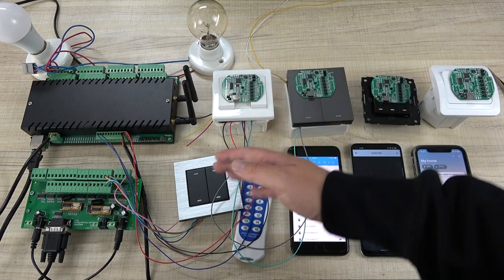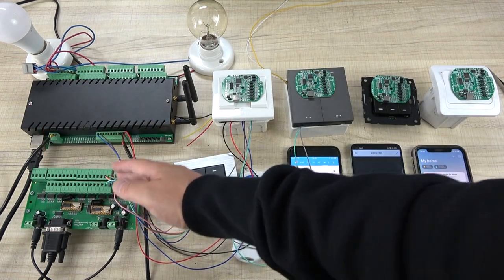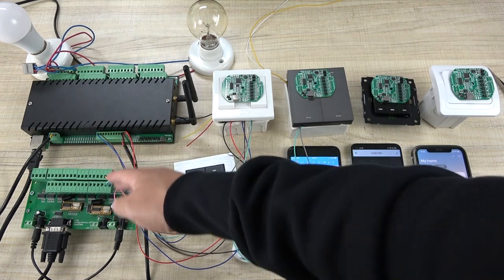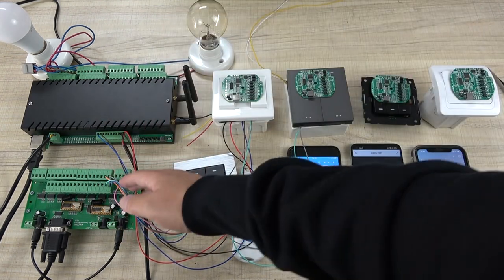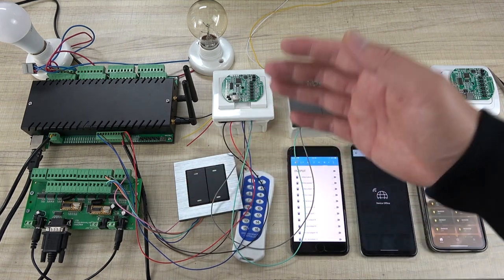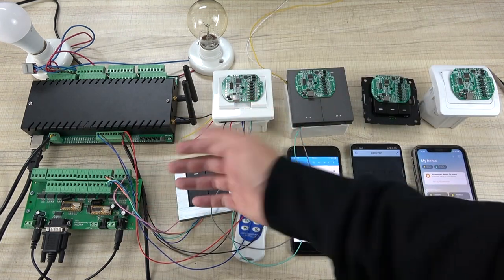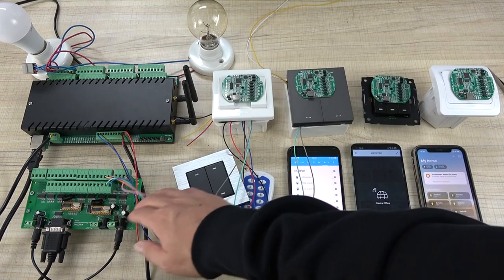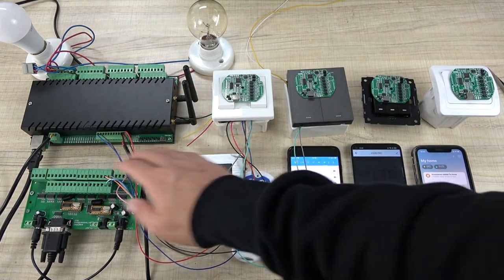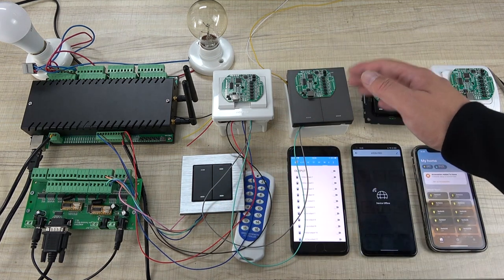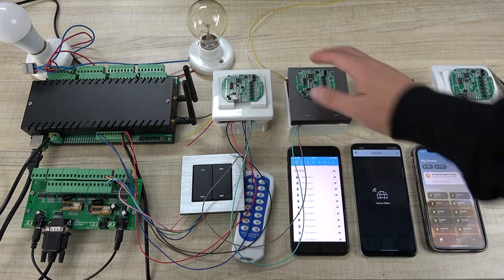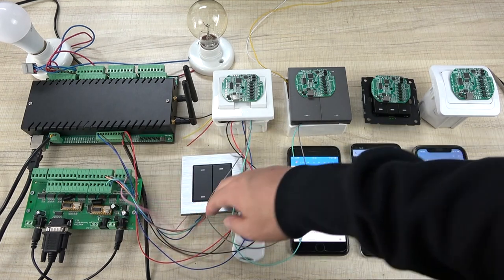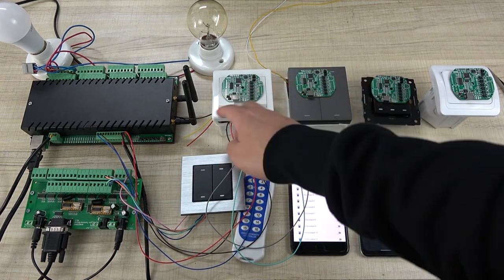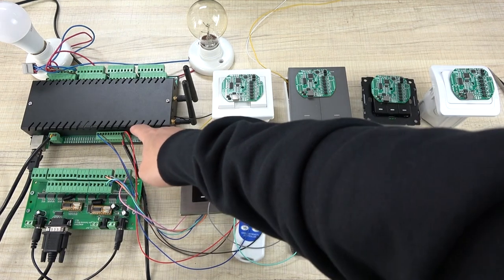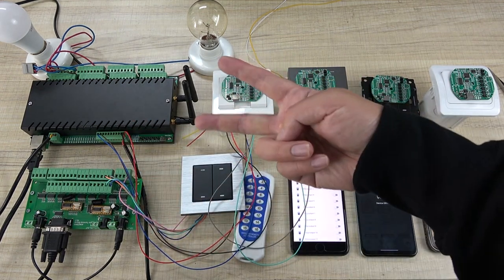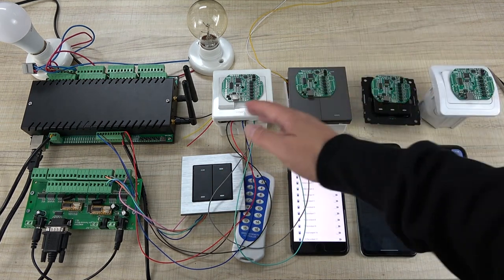And if you can, I suggest you use this way, just choose any dry contact. There is a lot of cable, so many cables, but it will be very stable, because there is no software and no communication protocol, just an on and off switch connected directly. In some projects and situations, you can't use so much LAN cable. So for some switches, you can use this RS485 solution and connect to this controller, so just only two wires. So that will be easy to place the new one.